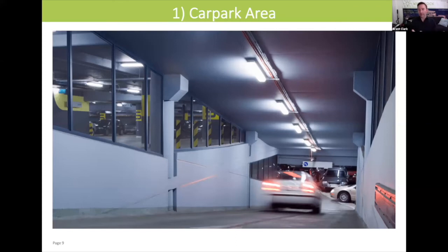And a recent innovation that's just come out in this last year is a 4-foot or 1200 millimeter batten light that actually has a half power mode. And by that, I mean, only every second LED dot can be illuminated with a little dip switch setting on that light. And the benefit of a 4-foot or 1200 millimeter motion sensored LED batten light is it spreads the light further while only consuming the same amount of power as the equivalent 2-foot light. And the benefit of this is it gets that light further to the back or where you might be getting the shopping out of the car.